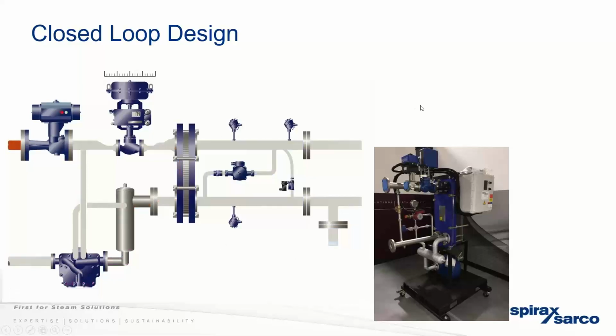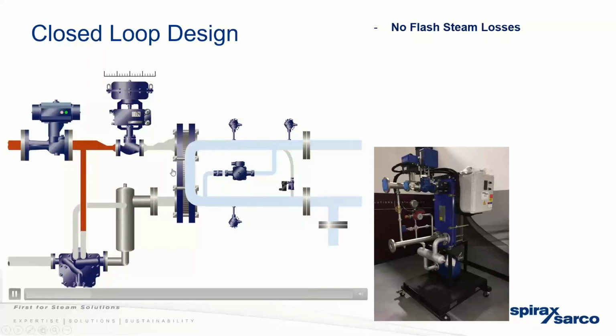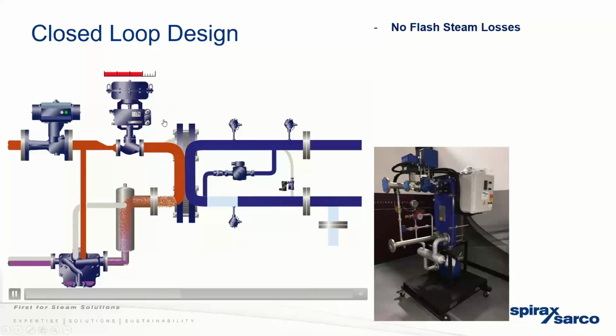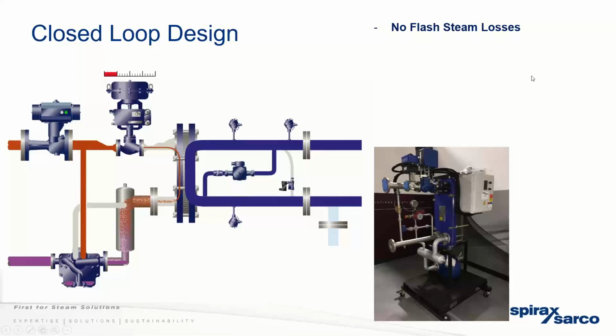With the closed loop design, the heat exchanger would be selected to operate under vacuum. And for that reason, we have a pump trap here. So this is using steam as the motive force. When the system's in vacuum, we don't have a vacuum breaker allowing air in. The pump uses the steam force to remove the condensate. So you can see condensate rising here, and the float in here is going to click open, saying, I need force. So it just opened up, it pushed steam into there, removed the condensate, and then it goes through a balancing process. So the pump trap allows this whole package to operate under vacuum without the introduction of air and to remove the condensate and still maintain tight temperature control.